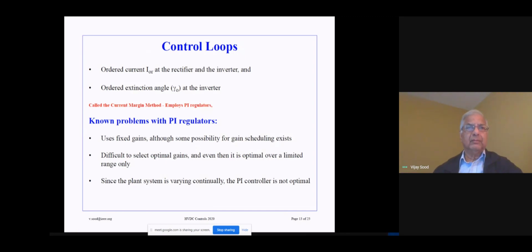There are some known problems with PI regulators. One of the problems is that these regulators use fixed gains. There is some possibility for some gain scheduling to take place. It is difficult to optimally select the gains. And even if the gains are selected, they are only optimal over a limited range. Since the HVDC system is continually changing, the PI controller settings are therefore not optimal over the whole range of operations. So these are some of the limitations that we know.